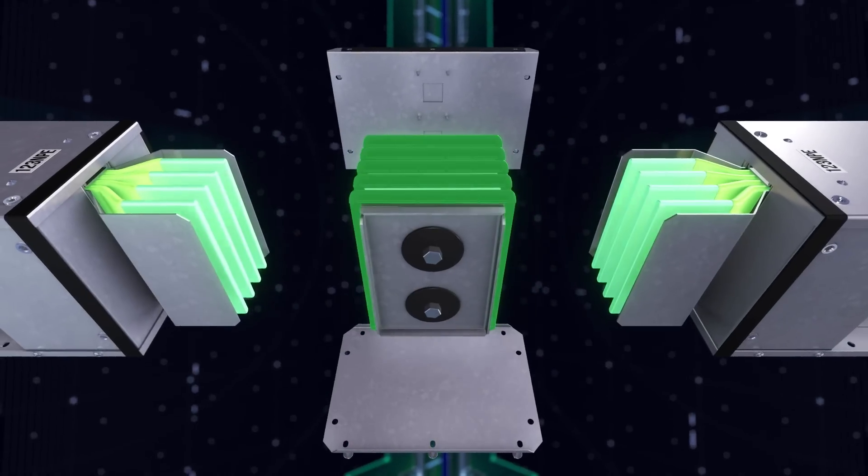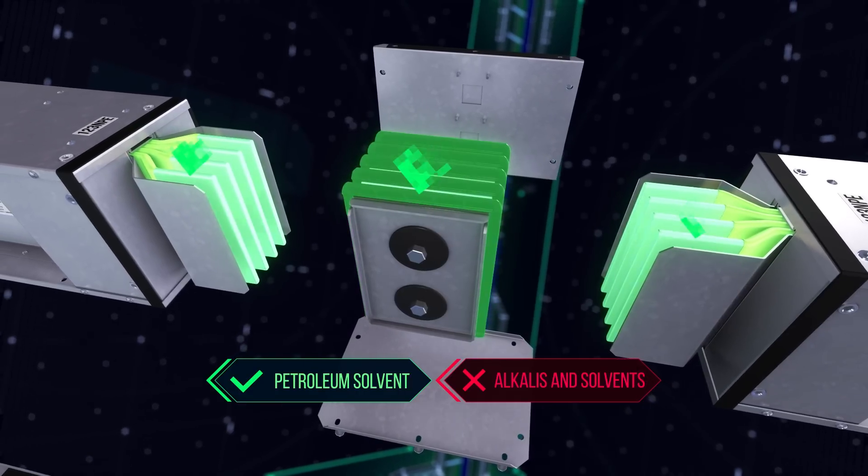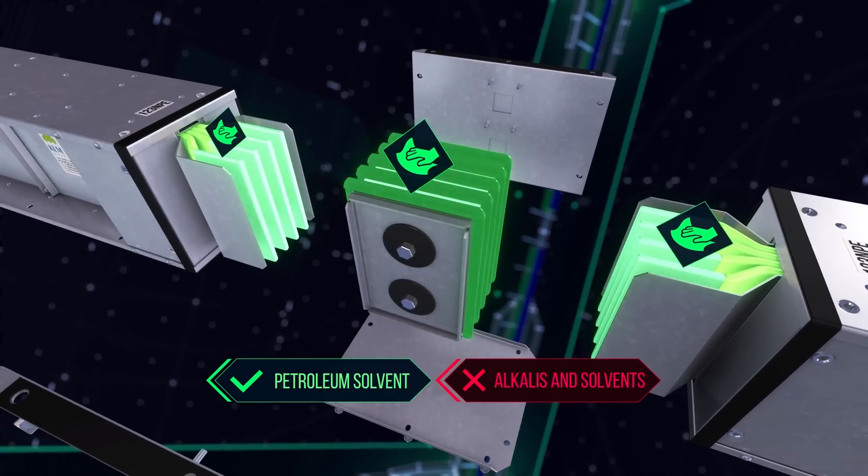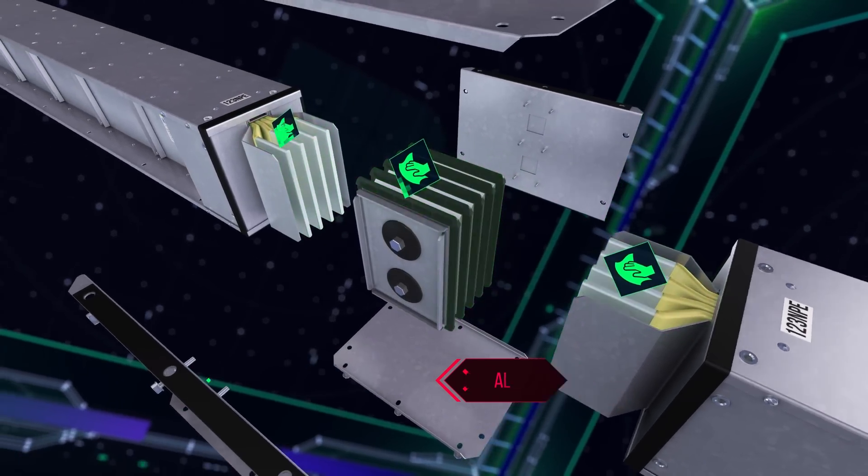Carefully inspect the current conducting parts of the bus bar trunking system sections and junction units. Clean them using a soft cloth and petroleum solvent or similar. Compounds containing alkalis and other solvents should not be used.